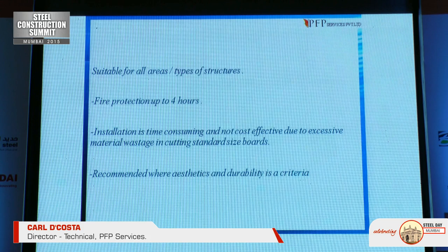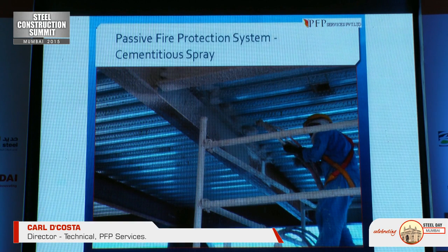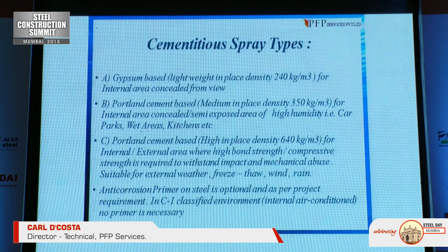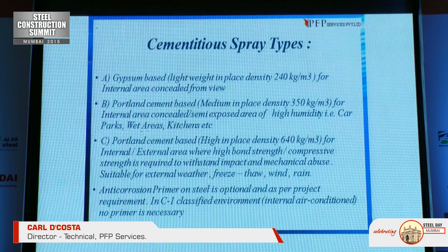Rigid boards are recommended wherever aesthetics and durability are criteria. The passive fire protection cementitious spray system is very popular now in India. We have a gypsum base — lightweight, in-place density of 240 kg/m³ — for internal concealed steel that is hidden behind false ceilings and panels. Then we have a Portland cement base — medium in-place density of 350 kg/m³ — for internal concealed and semi-exposed areas with high humidity, like car parks, wet areas, kitchens, etc.